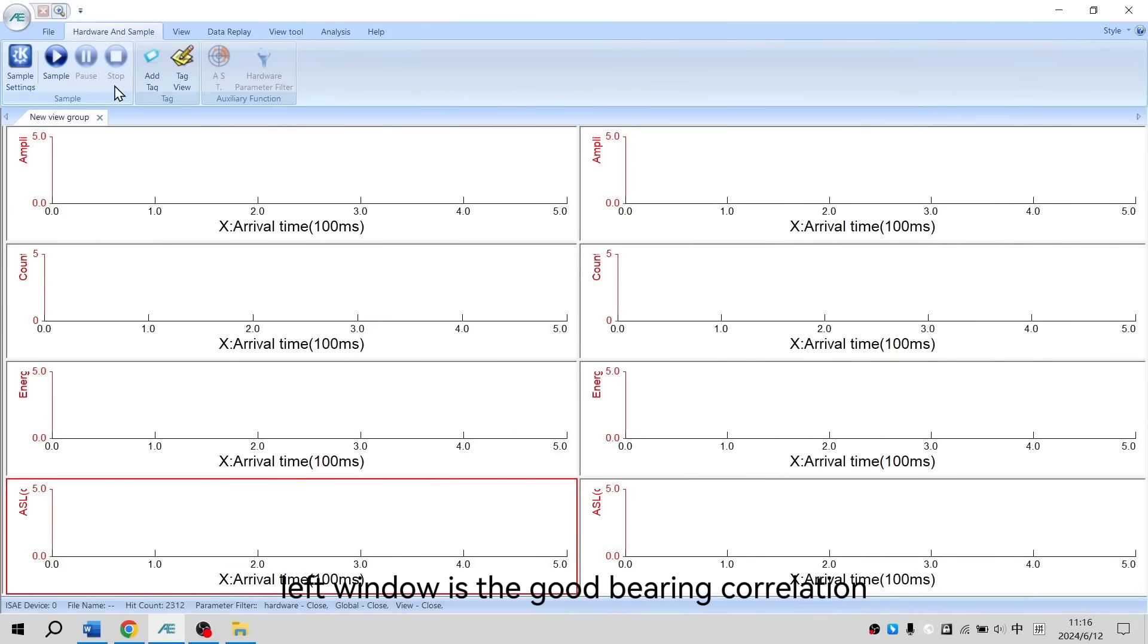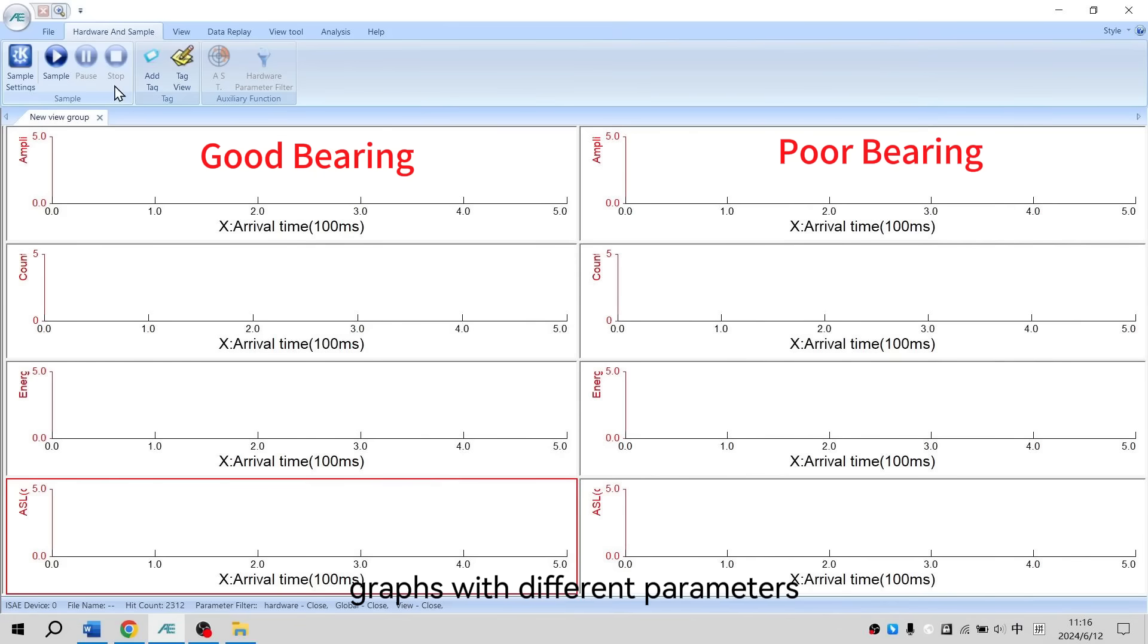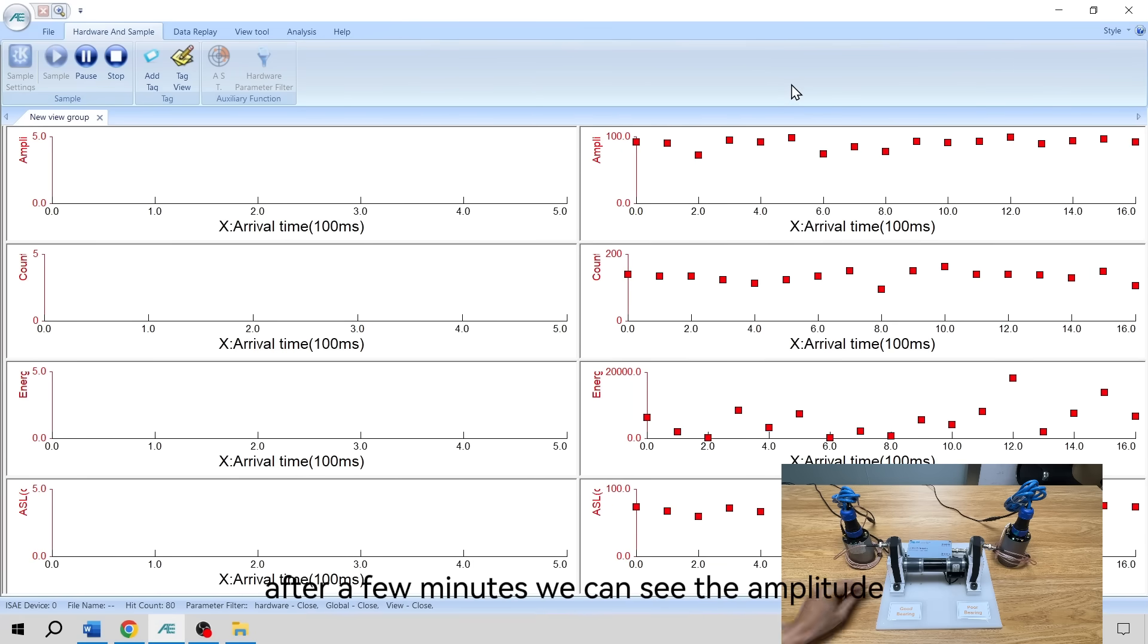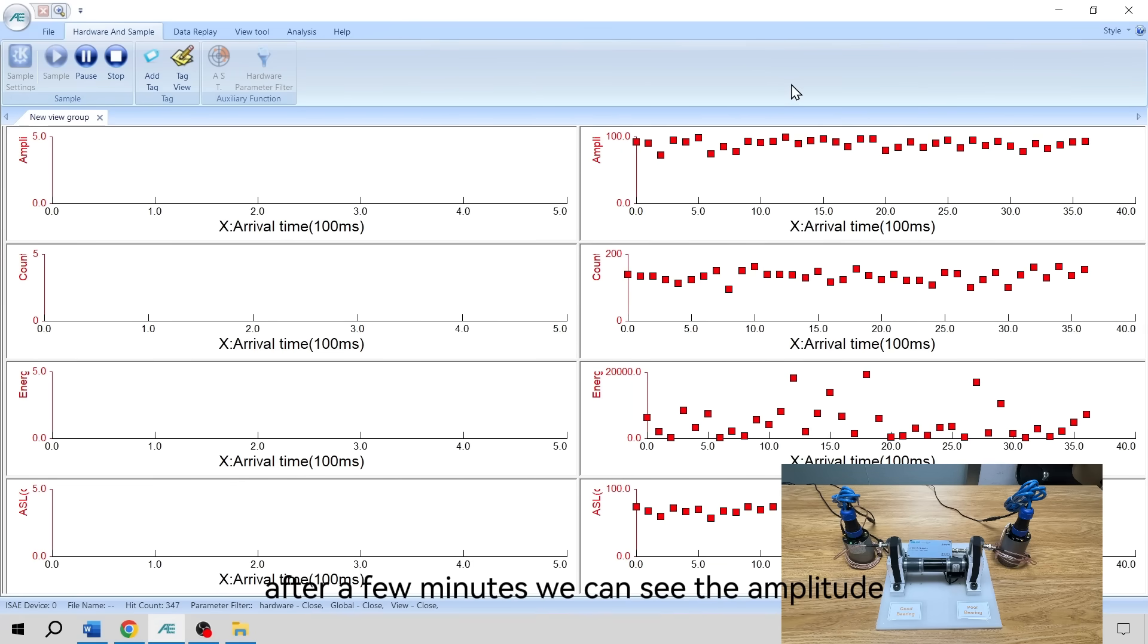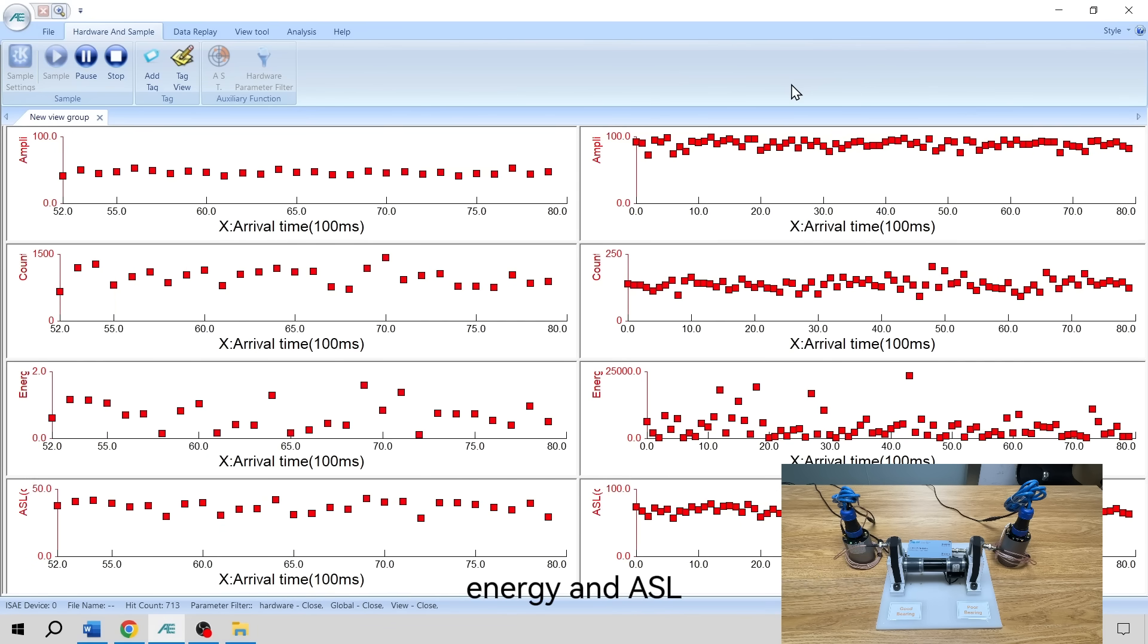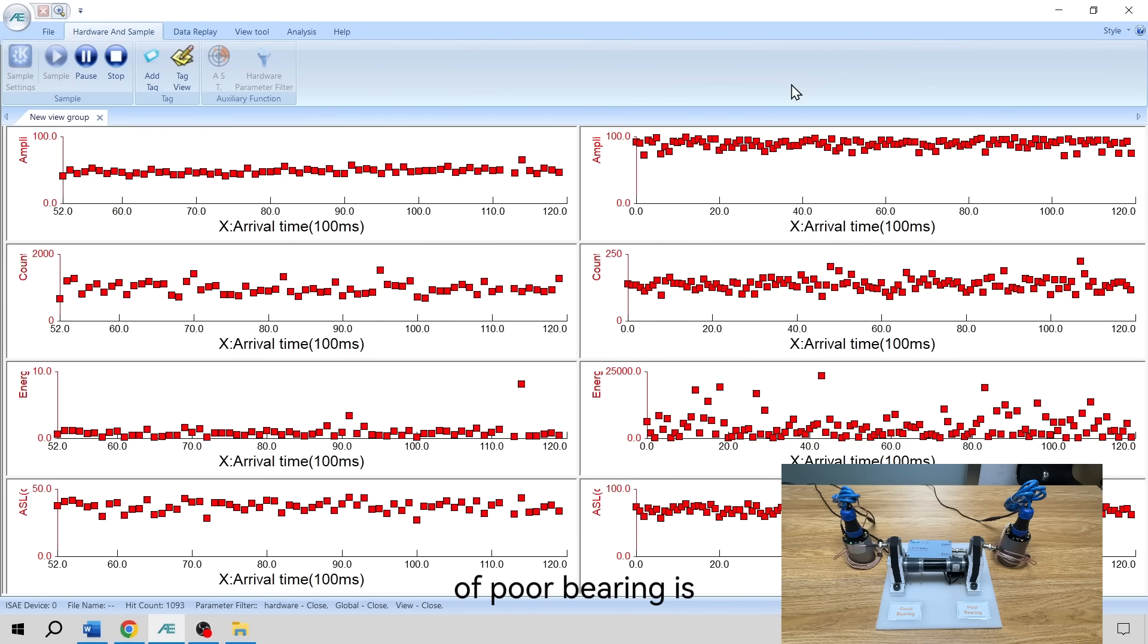The left window shows the good bearing correlation graphs and the right window shows the poor bearing correlation graphs with different parameters. Now we turn on the device and check the data. We can see the difference between the two graphs. After a few minutes, we can see the amplitude, energy, and ASL of the poor bearing.